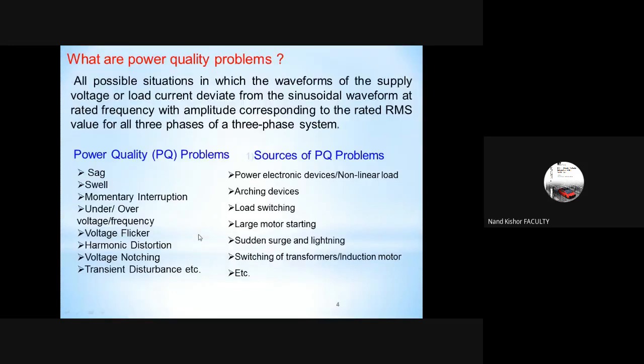Next in the DG system operation are the issues related to power quality. As per the definition, it covers all possible situations in which the supply waveform, either the voltage or the load current, deviates from the theoretical sinusoidal waveform at rated frequency and with amplitude corresponding to the rated RMS value for all three phases. That means if there is a deviation in the supply voltage signal from the sinusoidal form, in terms of amplitude corresponding to the RMS value for all these phases, that is a power quality problem.